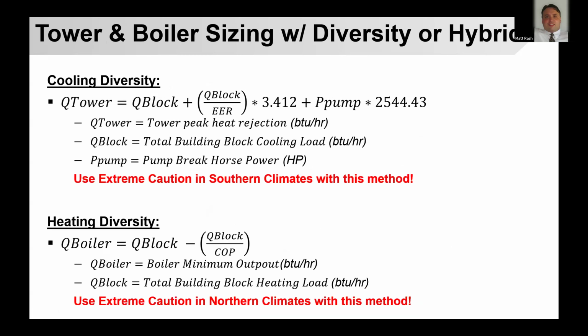I think one of the bigger advantages with this product with geothermal is where you can consider hybrid type geothermal systems where you have towers to help supplement that geothermal loop. That kind of drives down the cost and the size of that well field in many cases. We always get a lot of questions on how do we size for diversity or partial heat rejection or absorption if you want a backup boiler or a backup tower. And these are really basic formulas, and these apply to almost any manufacturer's geothermal equipment. It's basically just that diversified block load that really has to come from the engineer of record for your tower rejection, and then that block load divided by the EER multiplied by 3.412.